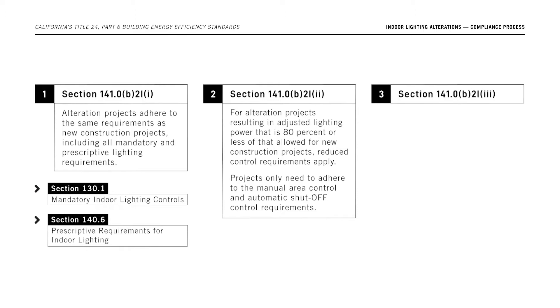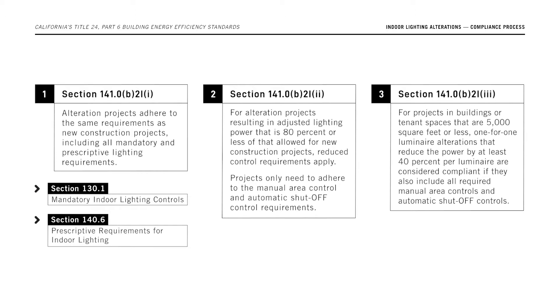Option 3: For projects in buildings or tenant spaces that are 5,000 square feet or less, one-for-one luminaire alterations that reduce the power by at least 40% per luminaire are considered compliant if they also include all required manual area controls and automatic shutoff controls.